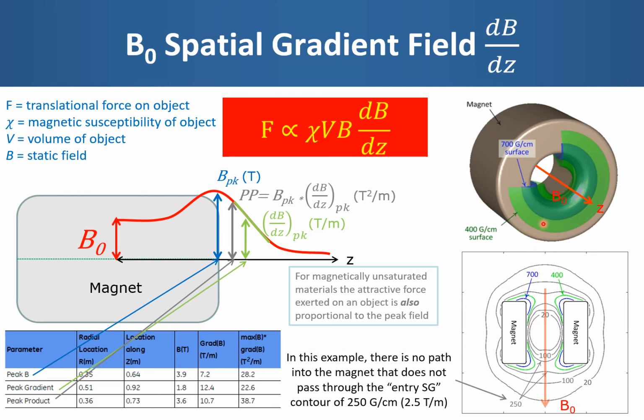But if a patient were to be entered into this magnet with an implant of some description, there is no path into the magnet that does not pass through the entry spatial gradient contour, in this case of 250 Gauss per centimetre, or 2.5 Tesla per meter. Manufacturers are also required to provide measurements of the distance from the center of the magnet to the peak field, the position of the peak gradient, and the product of the peak field and the peak gradient.